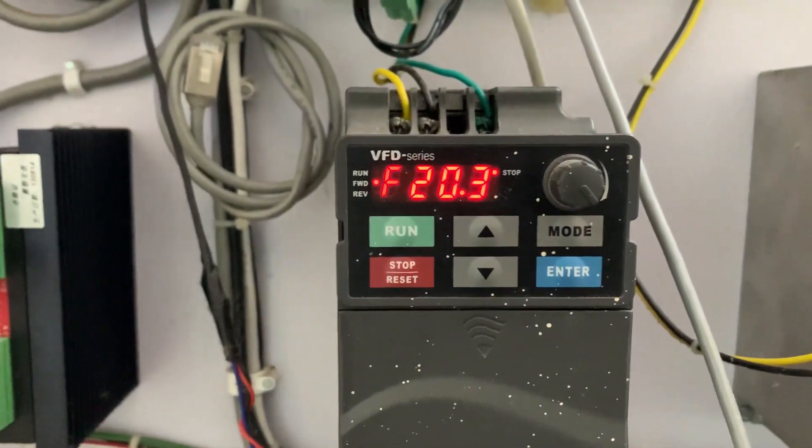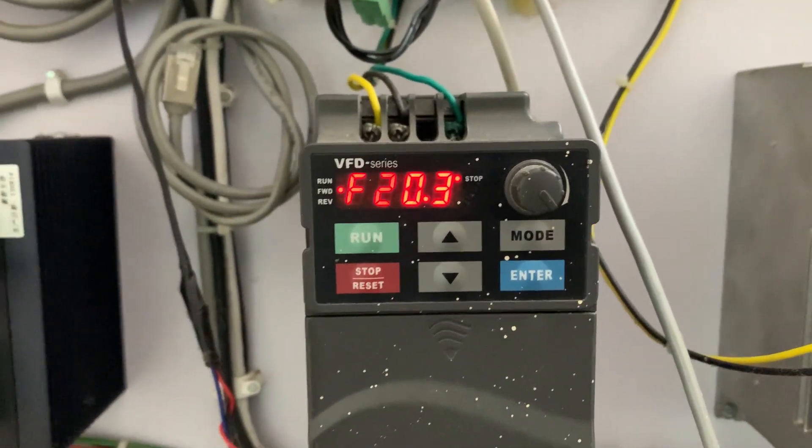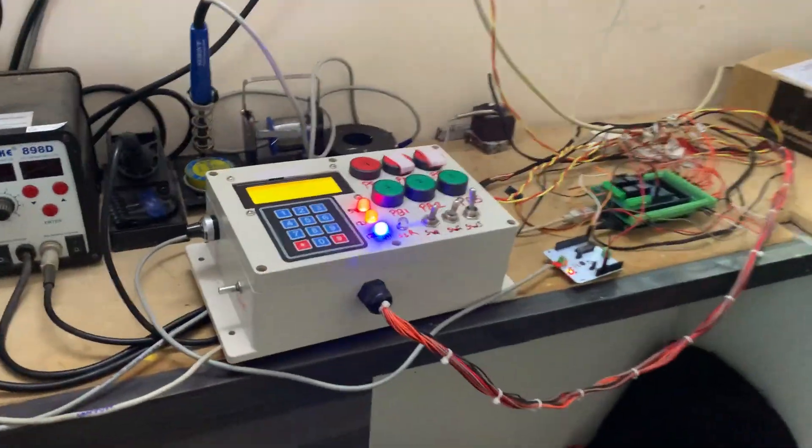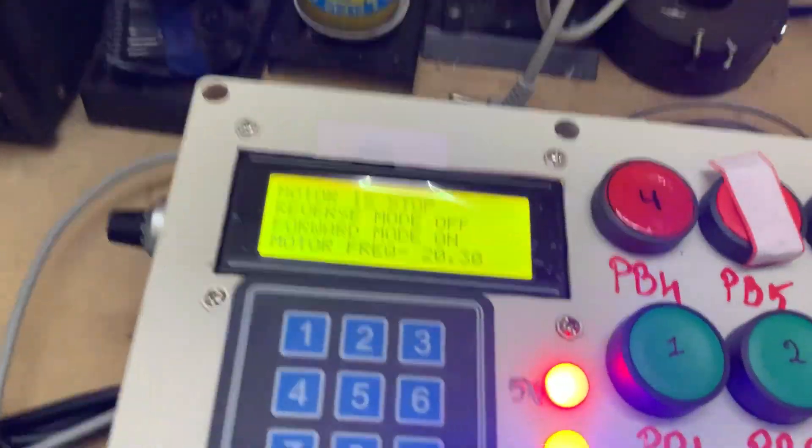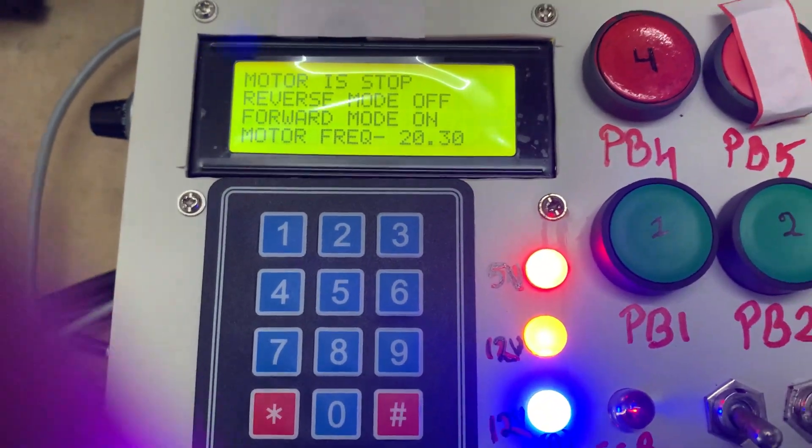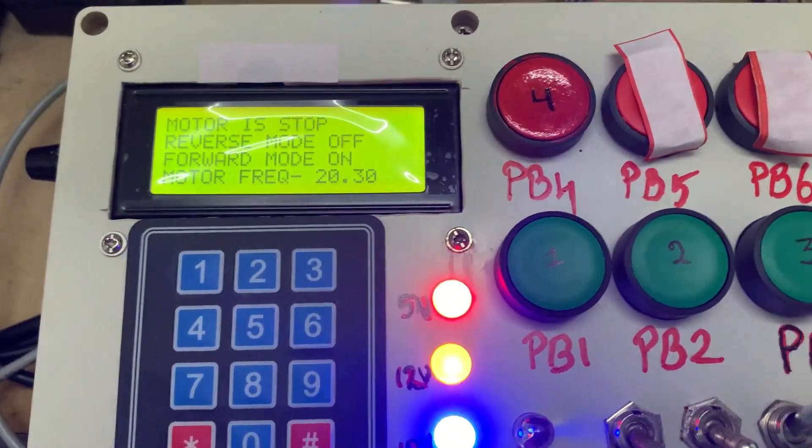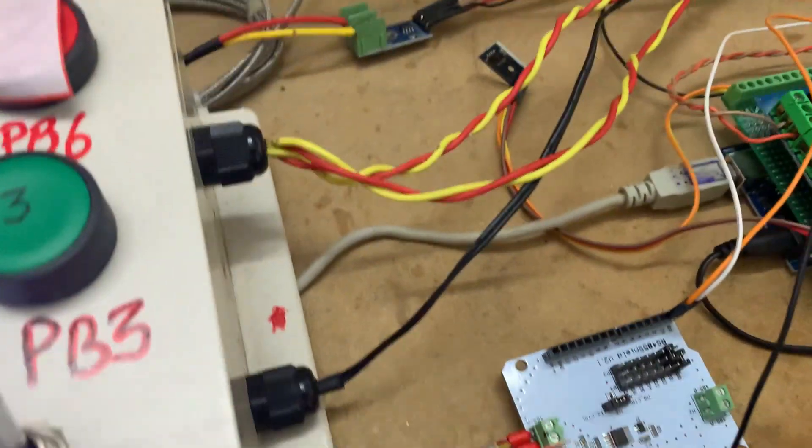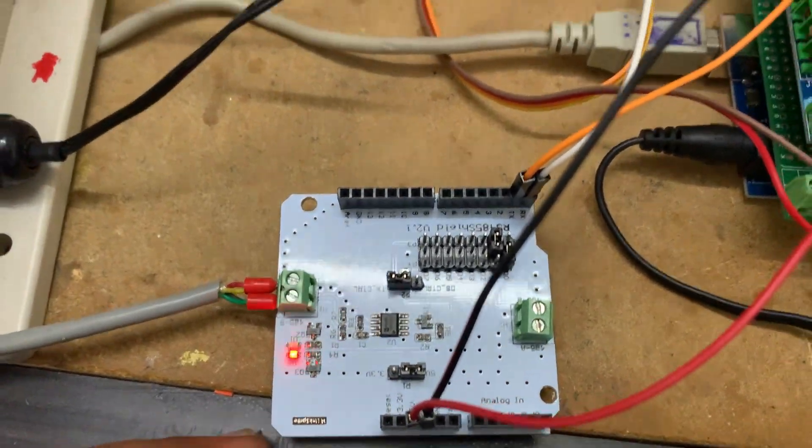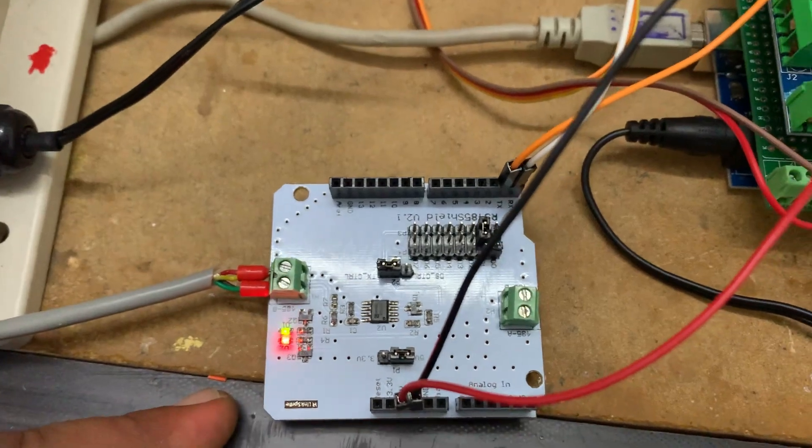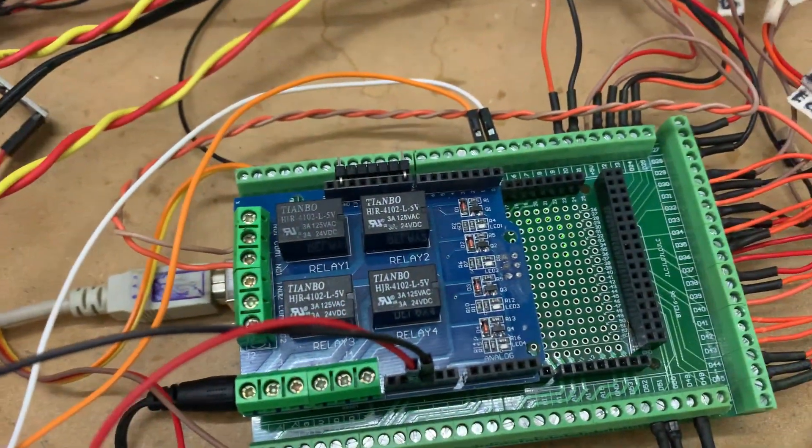The VFD here, as you see, the VFD is powered on. Presently the frequency is 20.3. I will show you my setup here. This one is my setup for controlling the motor, and that VFD is connected through Modbus by this RS-485 converter.